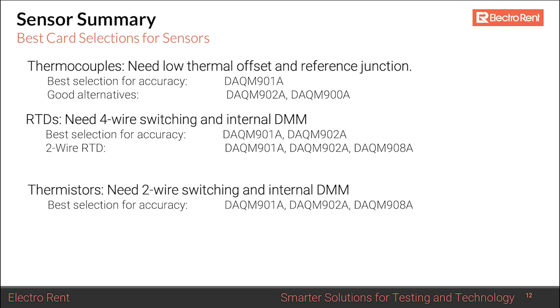RTDs generally require four-wire switching — and even three-wire RTDs still need four-wire switching capability — so the best cards are the DAQM901A and DAQM902A. For two-wire RTDs, the DAQM908A can also be used. Thermistors only need two-wire measurement with a standard resistance measurement, as they typically have around 5000 ohms resistance. Suitable cards for thermistors include the DAQM901A, DAQM902A, and DAQM908A.